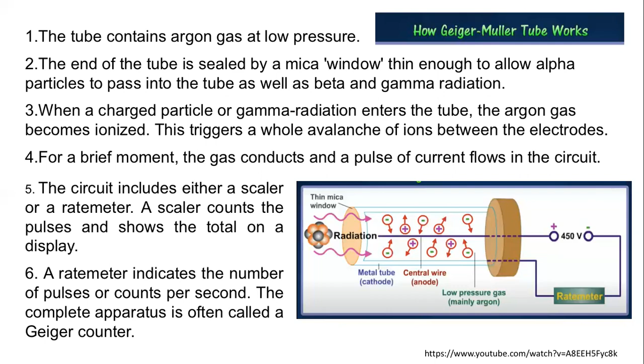So what is happening here? When radiation enters the Geiger-Muller tube, the gas inside the tube, for example argon, gets ionized, and once it is ionized, an avalanche of ions is formed within this tube, which creates an electrical pulse. This electrical pulse is sensed by the electrodes and passed on to the rate meter, which can measure exactly how many pulses or counts are coming per second, and this is a measurement of radioactivity. So this is how the Geiger-Muller counter works in detecting radiation.